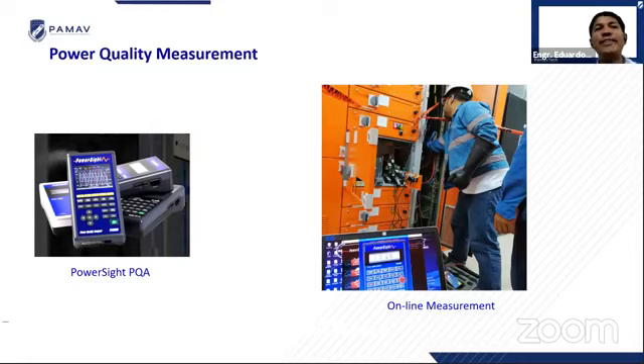So what is the difference between the spot measurement and the long measurement? Sometimes the operation in the plants is not continuous. We have a motor that starts only during daytime and during nighttime it is stopped. So if you only do a spot measurement, you cannot trend. My recommendation is that 24 hours or up to 1 week is the best measurement to be conducted in your system. Again, you need to have a caution tag, and only a qualified technician or engineer should perform the power quality measurement. Sometimes if the plant is so strict, they will implement whole body PPE because of arc flash. Remember, this is live.